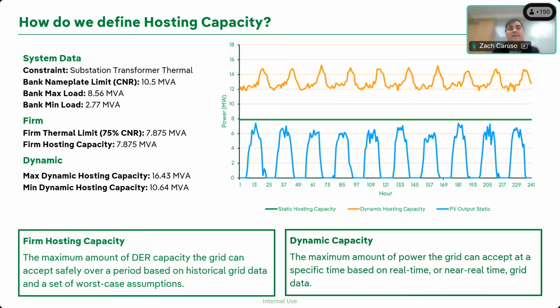we see that at, say, the peak hour, that most sunny hour of the year in the middle of July, the distribution grid actually probably has more capacity to accommodate additional PV or DER generation, because we are currently still a summer peaking utility. We probably have a fair bit of load there because it's a hot day and everyone has their AC on, and that load helps soak up some of that generation locally so that less power is flowing through whatever the constrained piece of equipment is. Therefore, if there were additional installed solar sites on the circuit, they could output at that time and take advantage of that additional capacity.